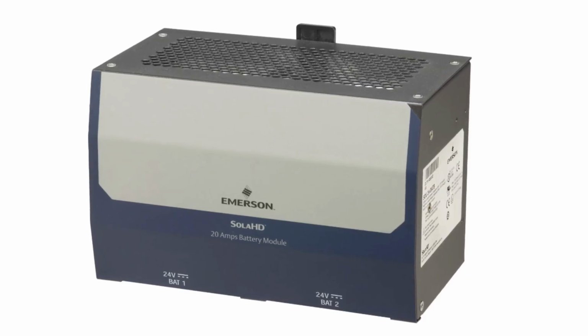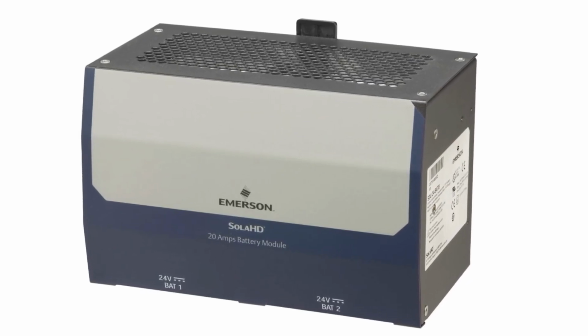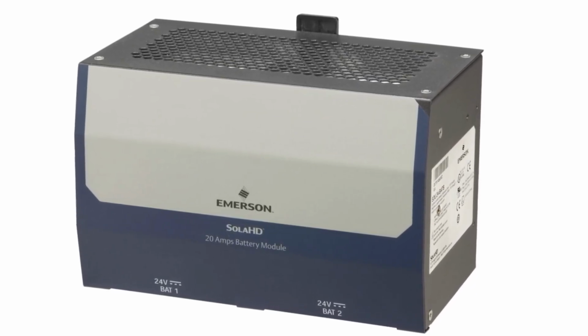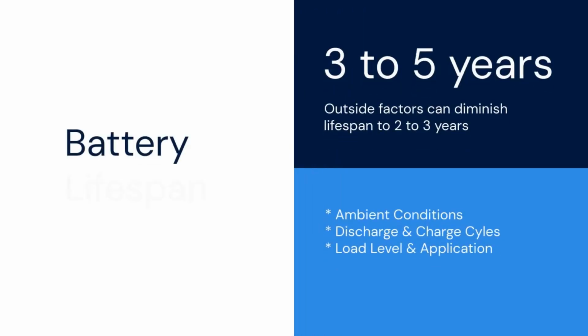All UPS have batteries that are essential in providing the required battery runtime to connected electrical devices. Typically, UPS batteries should last 3 to 5 years. However, outside factors like ambient temperature, load level, depth of discharge, and charge and discharge cycles, among others, can diminish the UPS battery life to 2 to 3 years.